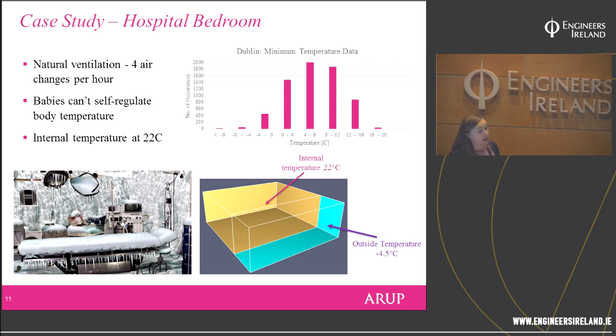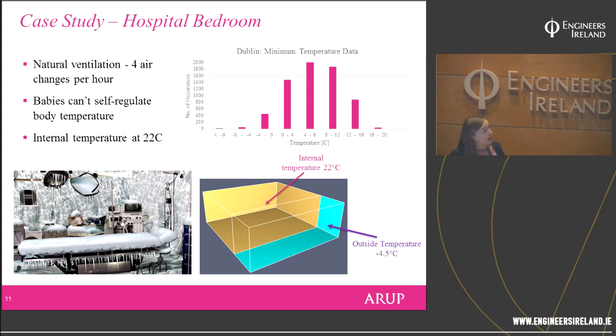Another interesting thermal comfort project involved a hospital bedroom. For this design it was hoped that natural ventilation rather than mechanical ventilation could be used — windows would open and close, providing the four air changes per hour required for fresh air. It was particularly important to maintain a minimum temperature of 22 degrees Celsius, as babies are not good at self-regulating body temperature.